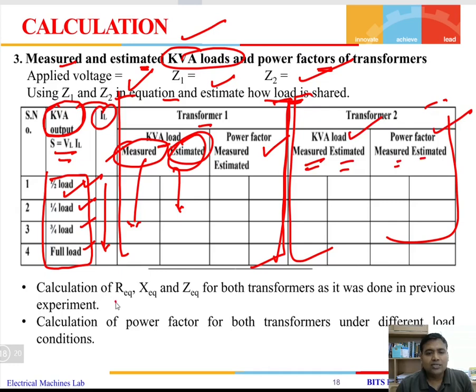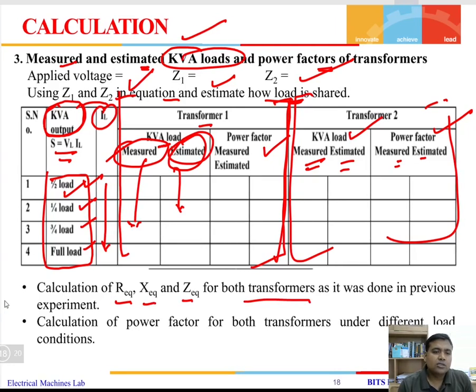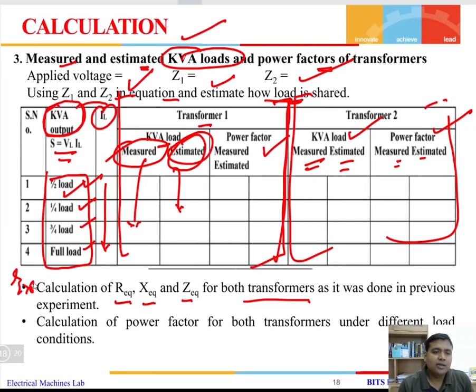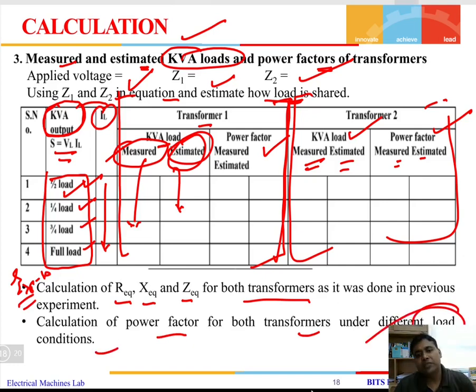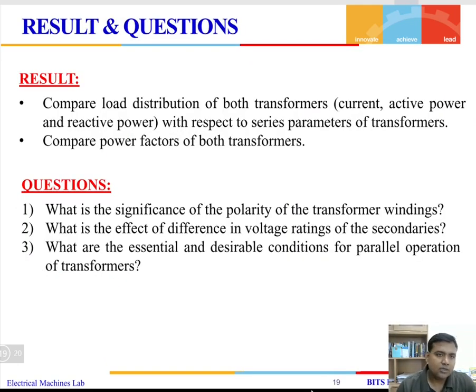Now you calculate the R equivalent, X equivalent and Z equivalent for both transformers, similar to what we have done for experiment number 10. So you follow experiment number 10 to do the short circuit test and calculation of power factor for both transformers under different load conditions. When the load changes, obviously the power factor will change because there will be a change in the current and voltage angle. Now just write the result.